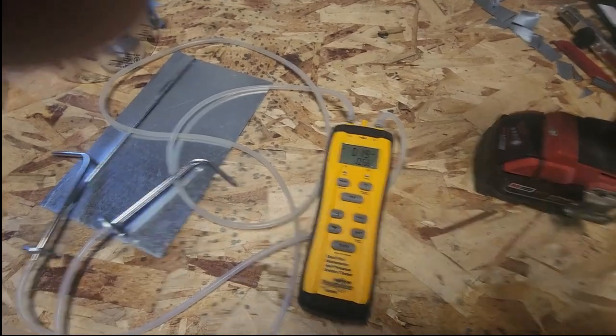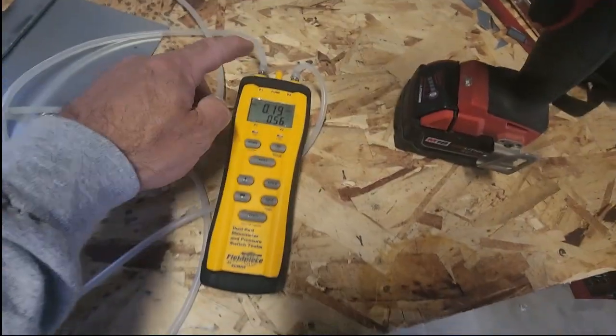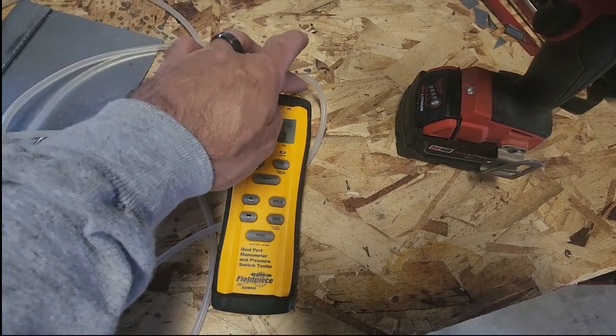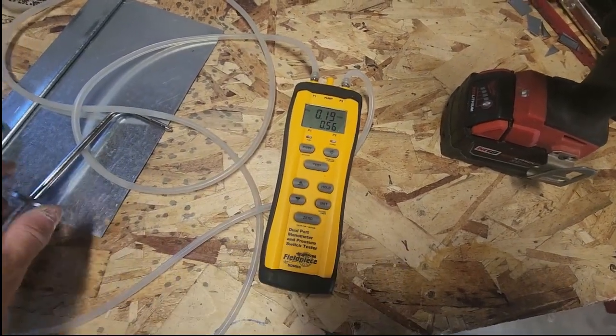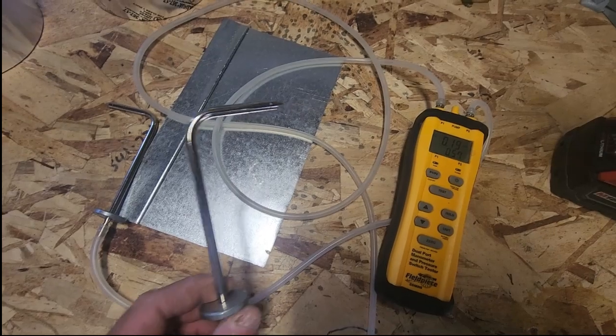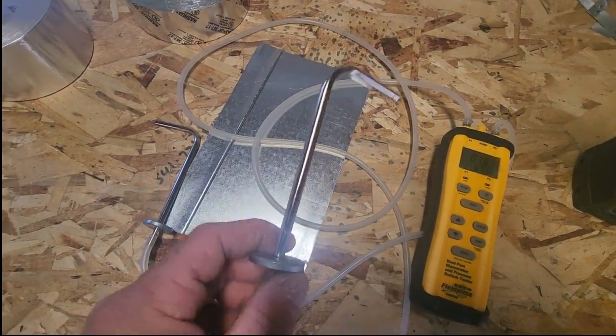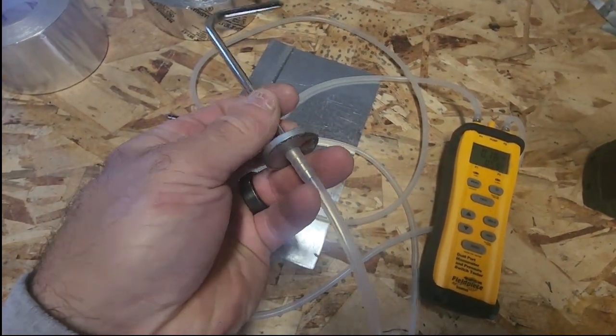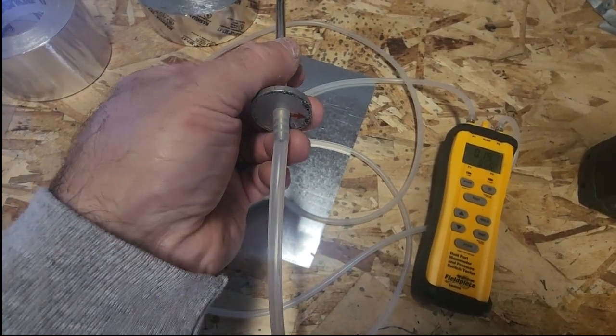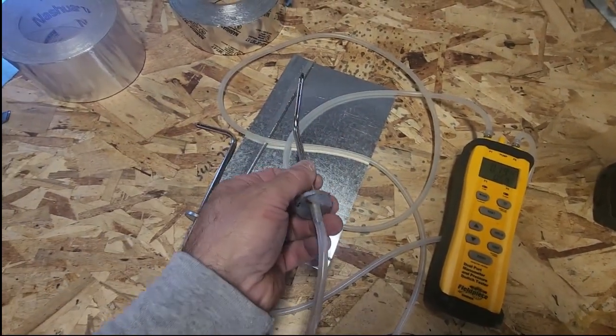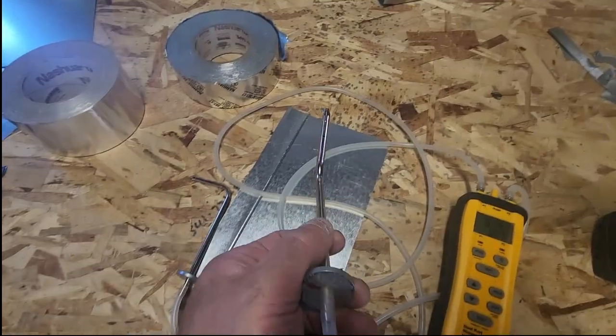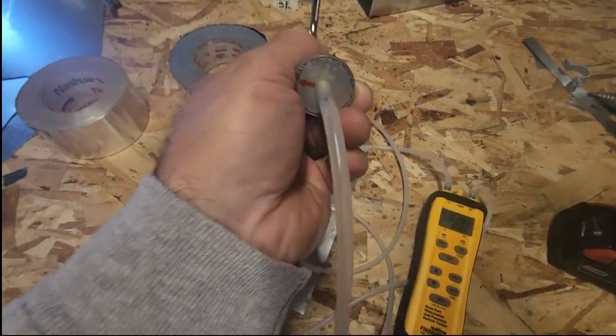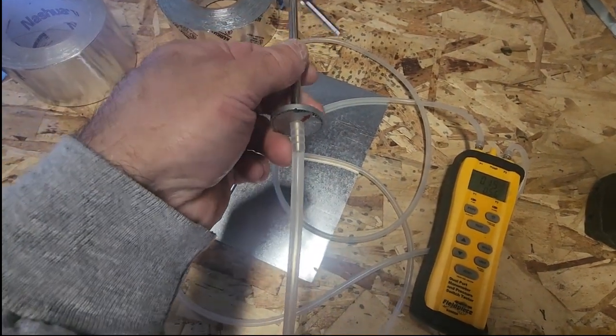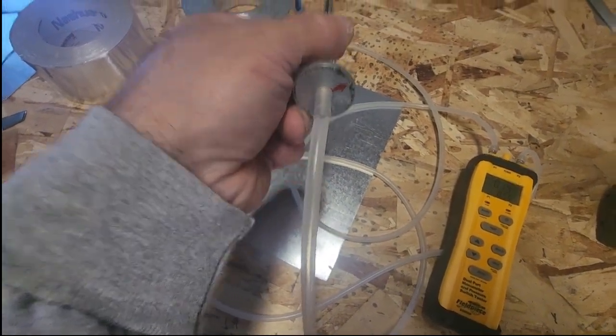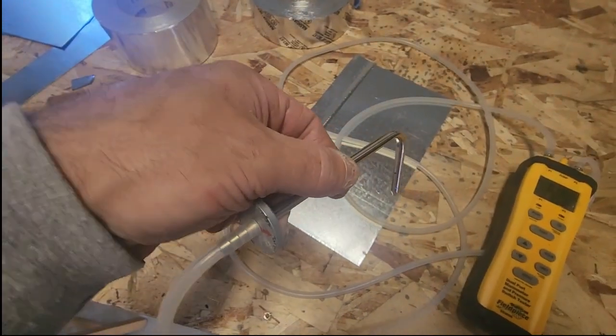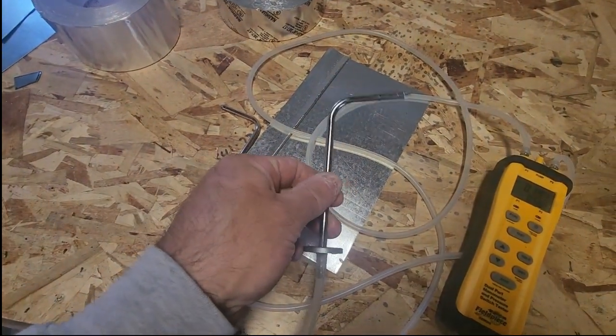So what you need is your manometer and your length of tubing to go into port 1 and port 2. This is going to be one for the supply and one for the return duct. Each one has a static pressure tip, and these tips must point into the airstream. Mine's kind of screwed up, the swivel on it is broken, so I'll have to make sure it's going into the airflow. On my downflow air handler, it needs to point up like that, and the same with the return. If you had an upflow, it'd be opposite, so you'd have your tip pointing down and your return pointing down to orient it.